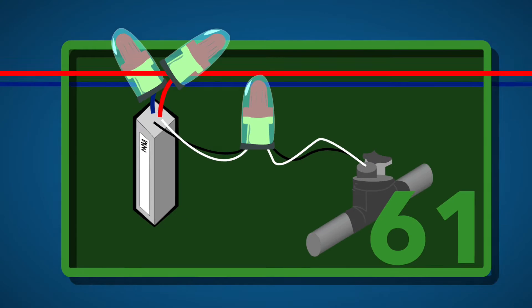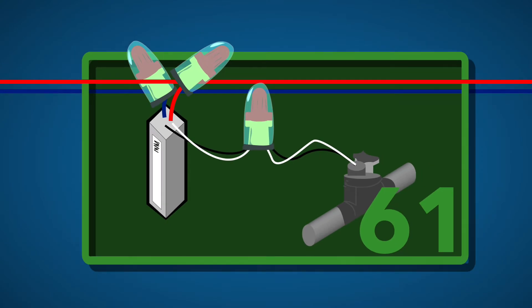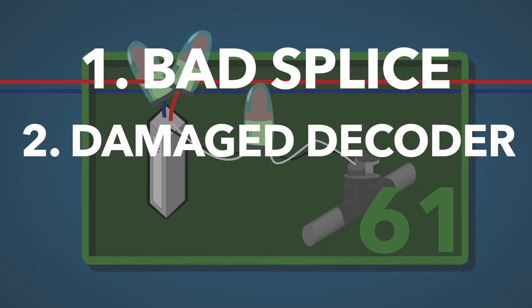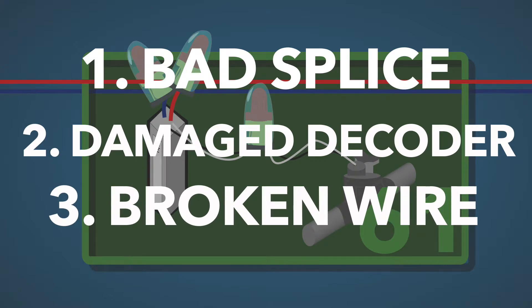Taking readings in this 61st valve box, we will probably find something other than 39 mA after this decoder. The troubleshooter can replace the splices or change the decoder to attempt to isolate the problem. It can be a bad splice, a damaged or bad decoder, or a problem in the wire itself.